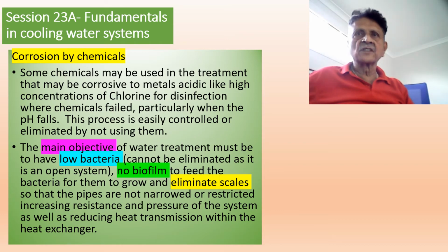A continuous layer of scales that form will eventually narrow or restrict the pipe, causes increasing resistance to the flow of water, causes increase in pressure of the system, and reduces the heat transmission within the heat exchanger.